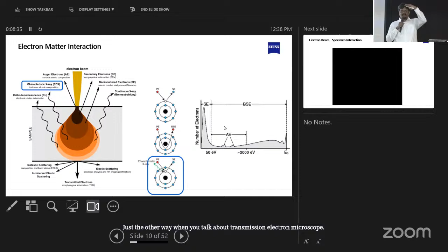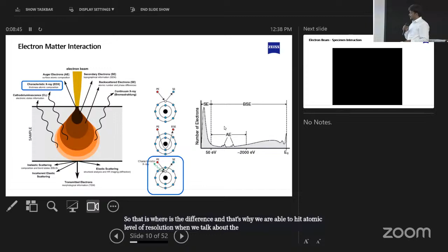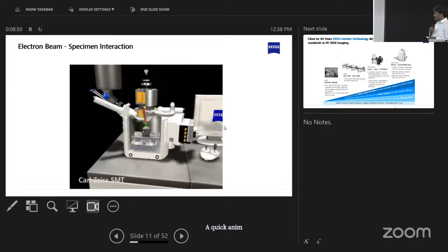One big difference is that when you're talking about a scanning electron microscope or field emission scanning electron microscope, all the information is collected from the sample surface. The other way around, with a transmission electron microscope, we collect information where the electron beam passes through the sample. That is the difference. And that's why we are able to hit atomic level resolution with the transmission electron microscope as well. Here is a quick animated video representation of what exactly happens.